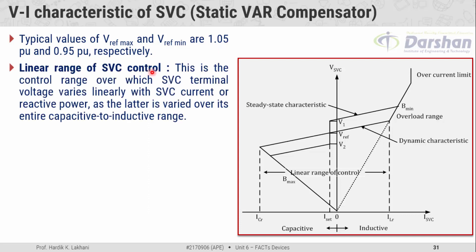The linear range of SVC control is the portion from one point to another that is known as the linear range of control. This is the control range over which the SVC terminal voltage linearly varies with SVC current or reactive power, when the magnitude of the current or reactive power varies over its entire capacitive-to-inductive range.